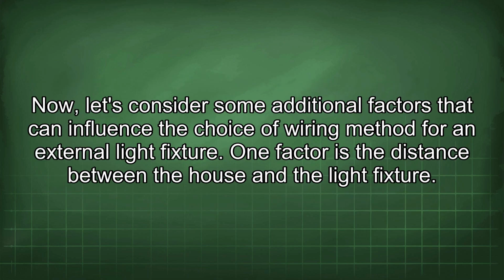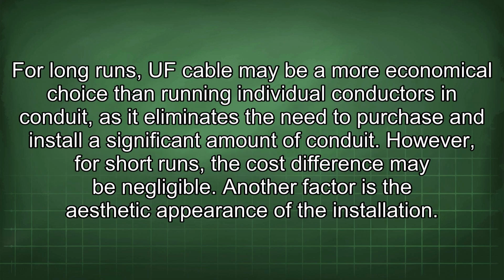Now let's consider some additional factors that can influence the choice of wiring method for an external light fixture. One factor is the distance between the house and the light fixture. For long runs, UF cable may be a more economical choice than running individual conductors in conduit, as it eliminates the need to purchase and install a significant amount of conduit. However, for short runs, the cost difference may be negligible.